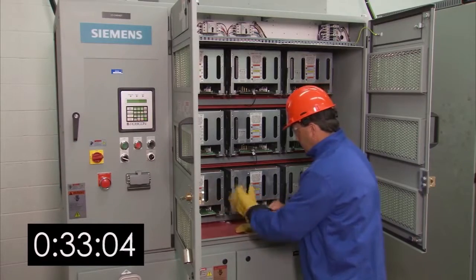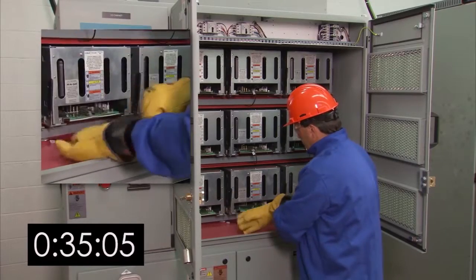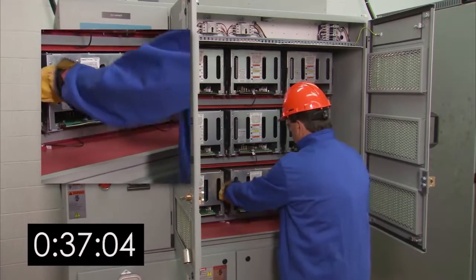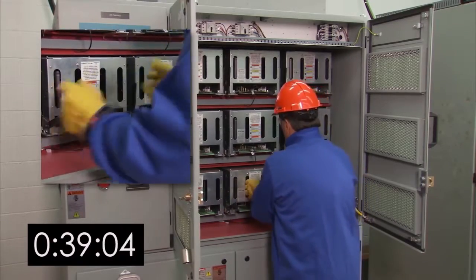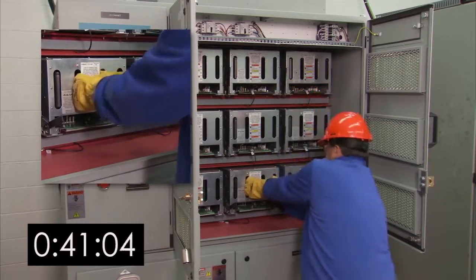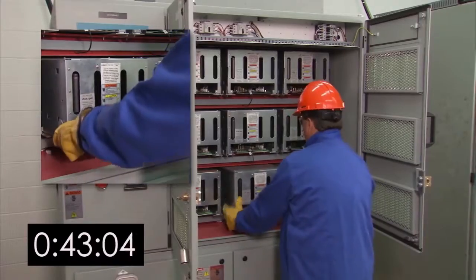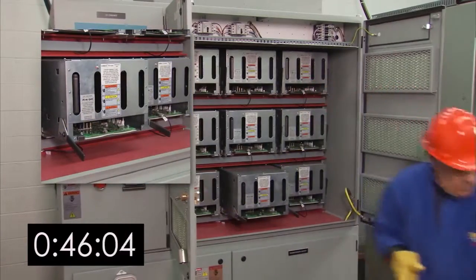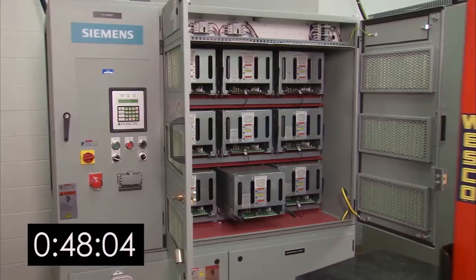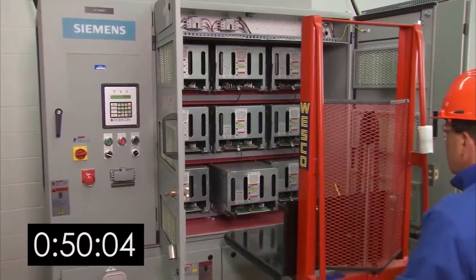Wearing low voltage gloves, pull the two cell handles down and firmly grip the power cell. Pull the cell partway out of the bay area, then put a cell lifter just under the power cell assembly. Now you'll be able to easily extract the cell and slide it onto the lifter.